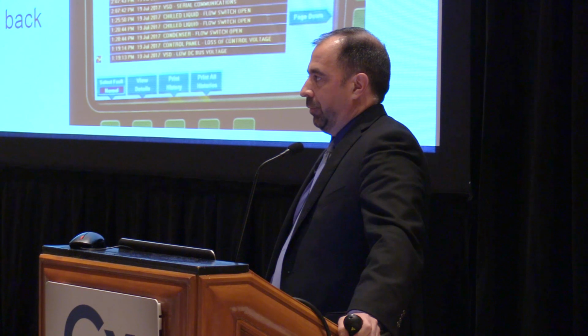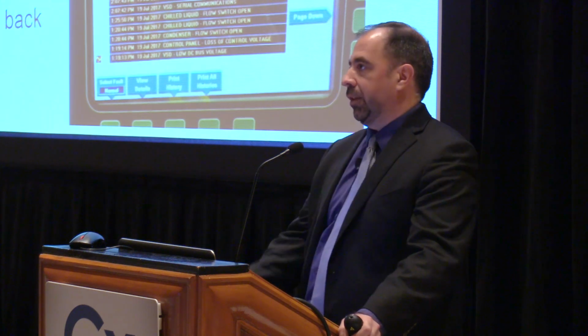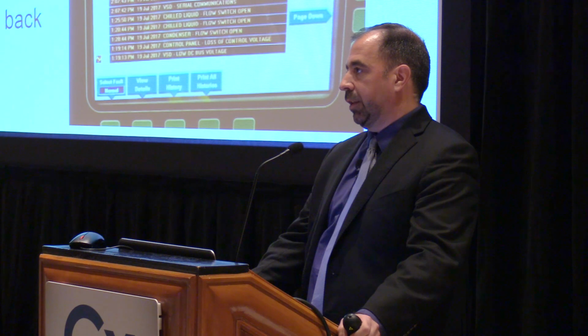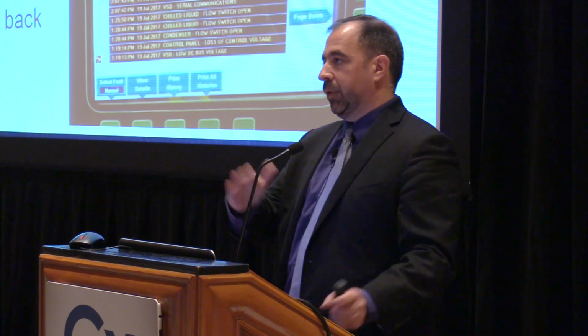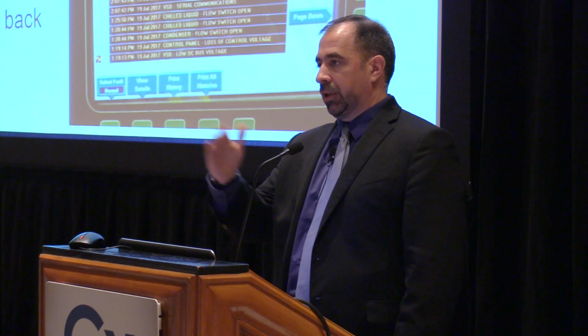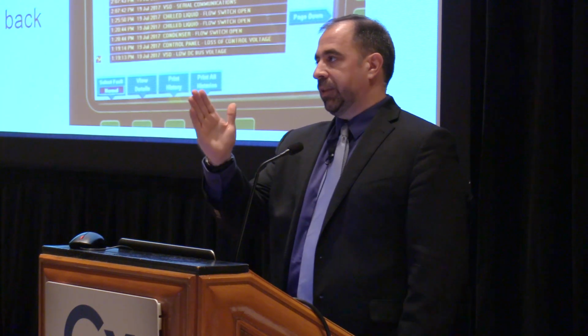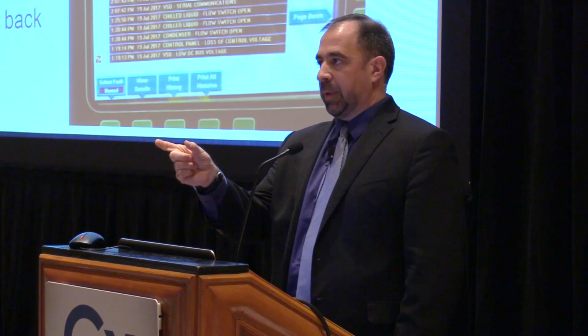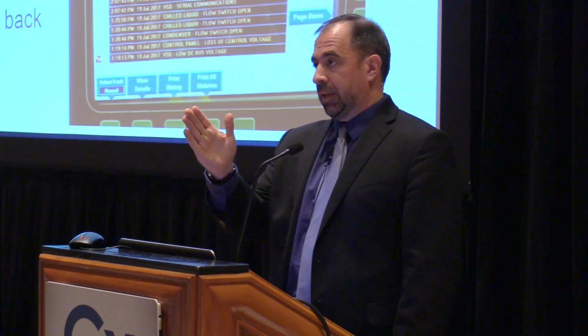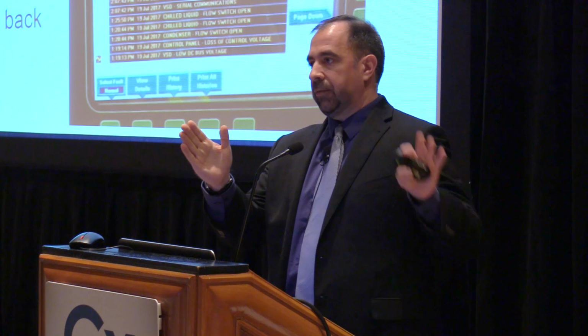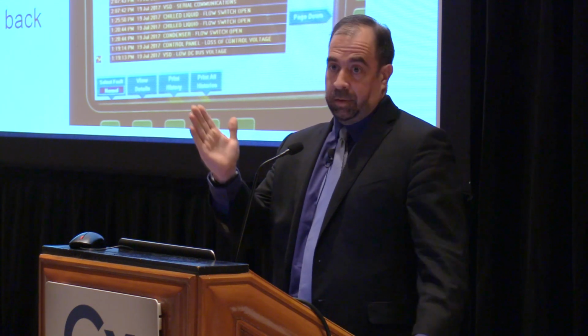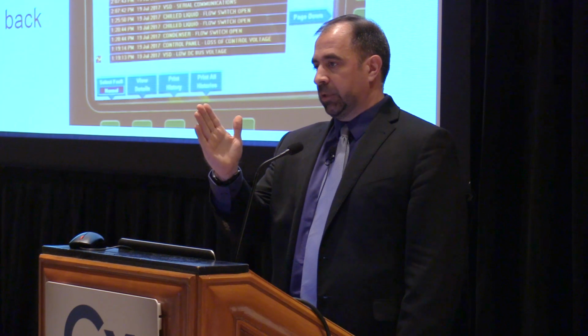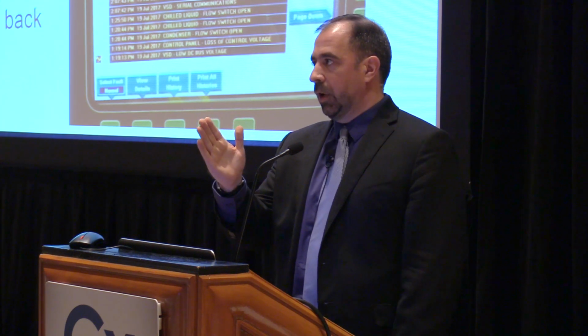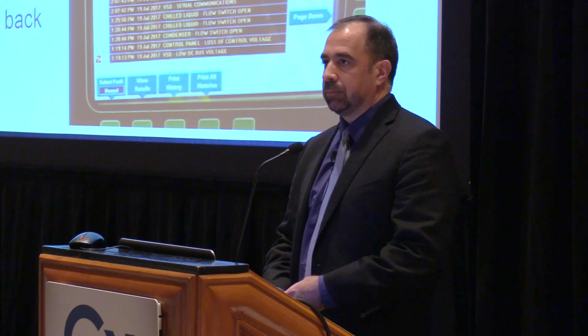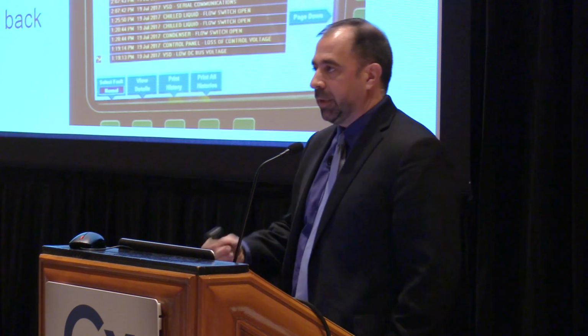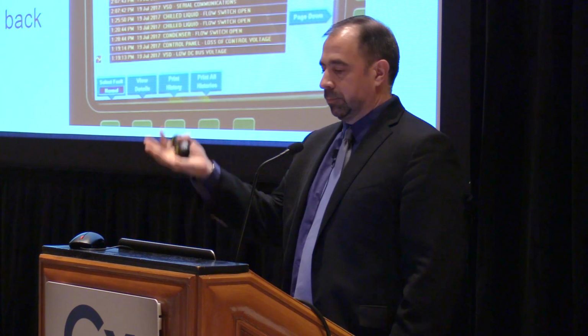It's a delay transition for a few seconds. We see that all the time on equipment branch where there's actually a delay. We purposefully delay. There's actually a center position, a center off position. So it's programmed where it goes from normal to this center off, where it's not connected to anything for some specified period of time. The code doesn't say it has to transfer within 10 seconds. Your life safety and your critical has to transfer within 10 seconds, but your equipment can take as long as you want. So you switch it to that center off position for however long you want, and then you switch to the emergency. So there's no reason to do a closed transition in that period because you're purposefully trying to have a delay.